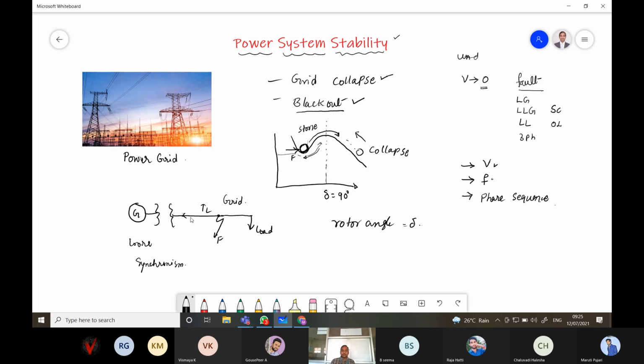By removing the fault. We use circuit breakers. The circuit breaker will operate and isolate the fault, so both the generator part or power system part and the fault part will get opened. The line will be open now. How fast the circuit breaker acts in isolating the fault from the healthy section matters. Before the grid collapses, the generator must come back within the steady state limit, that is the stability limit. Then we can achieve stability. It has to regain its original state and should not lose synchronism.